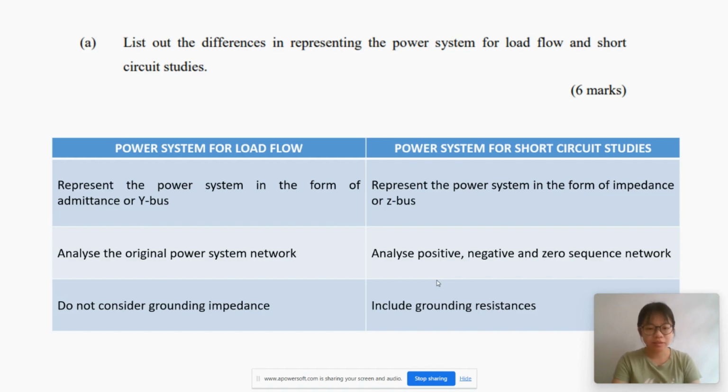The second difference is we only analyze the original power system network in the load flow study. However, for the short circuit studies, we are required to analyze the positive sequence network, negative sequence network, as well as zero sequence network.